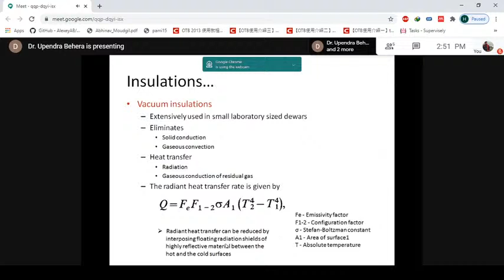Then, apart from this, in powder and fibrous insulation, the gaseous conduction is the primary mode of heat transfer. So the method to reduce that is to evacuate the gas from the insulation space. And you can see this graph, which gives the residual gas pressure in torr against the thermal conductivity of the insulation material.